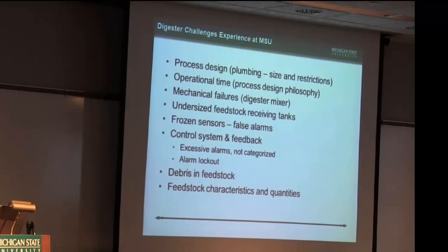There's always a little bit of debris that gets in there, and when your pipe sizes are so small or you have so many 90s in close proximity, clogging becomes a major issue. That's really been our biggest challenge over the last 2 years. This system was commissioned in October of 2013, so we're just a little bit over a year into operation.